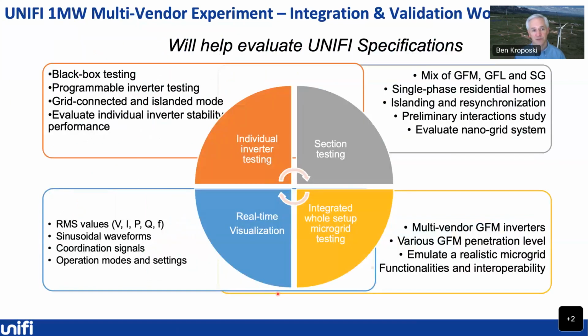Now, to go beyond that, we're starting to put together several actual hardware experiments. Our first one is a multi-vendor experiment at the 1 megawatt level, where we'll be able to set up individual inverter testing, evaluate their grid forming capabilities, but more importantly, look at multiples of different vendors, all trying to meet those specifications and verifying that these multi-vendor grid forming technologies can actually work together across a variety of scenarios. So both at this scale, at the 1 megawatt scale, we're interested in understanding how this mix of technologies work together. So whether it's single phase technologies, three-phase technologies, whether we're evaluating grid forming inverters or grid following inverters or synchronous generators, a variety of actual real world hardware connections to validate that these requirements will, at the end of the day, give you a working system.